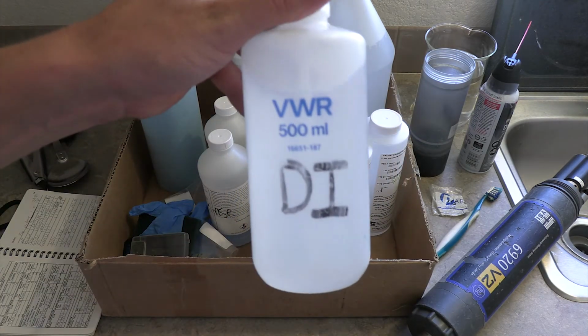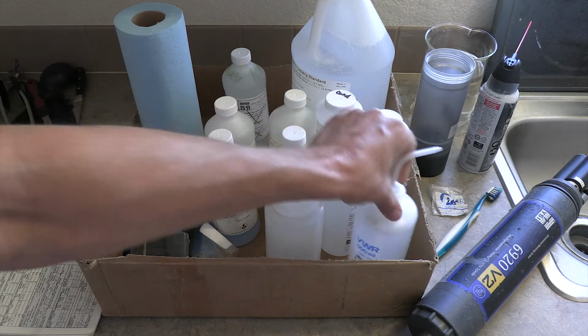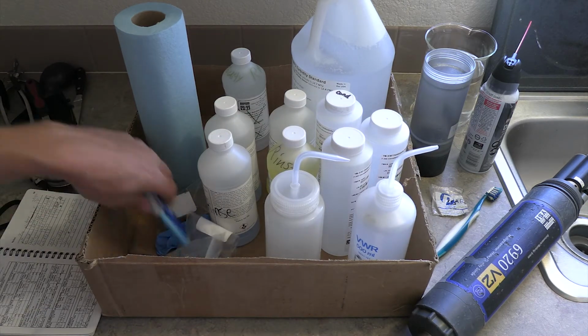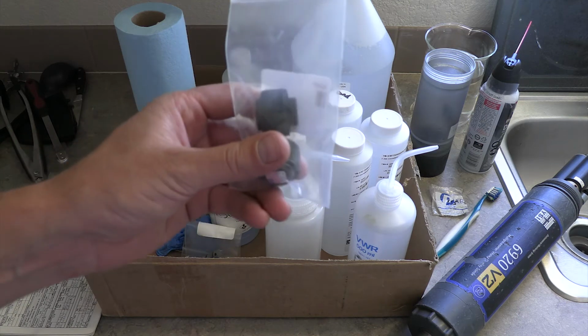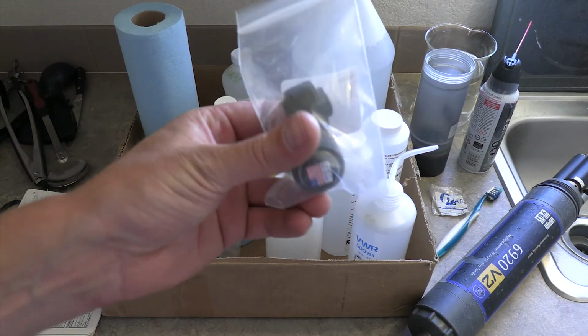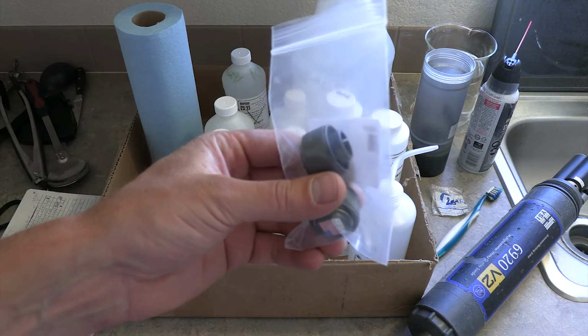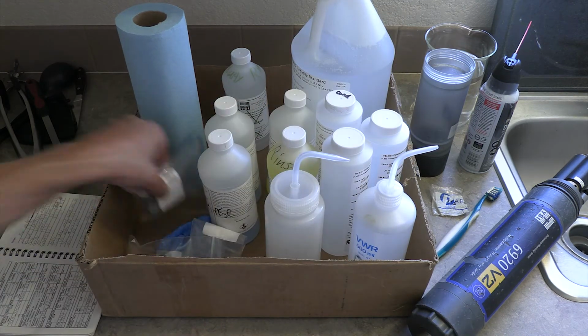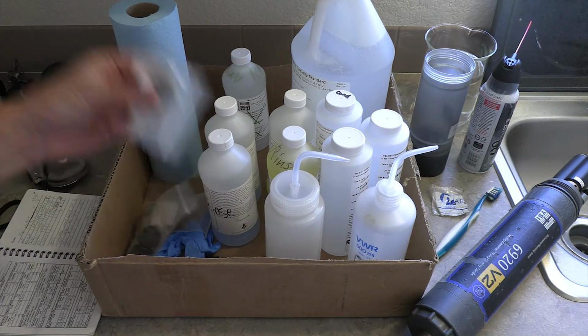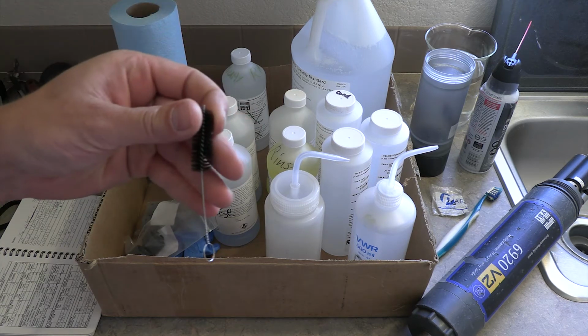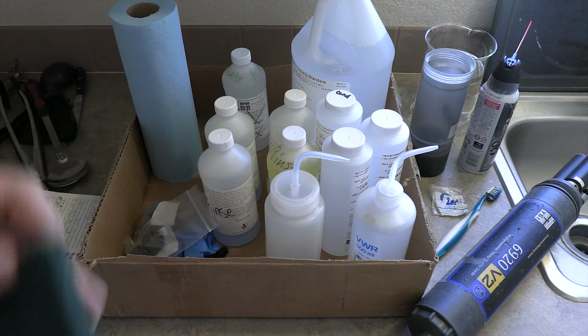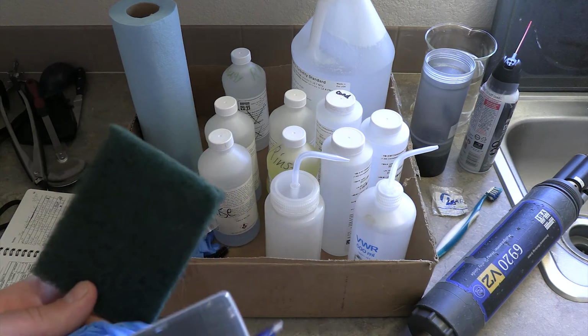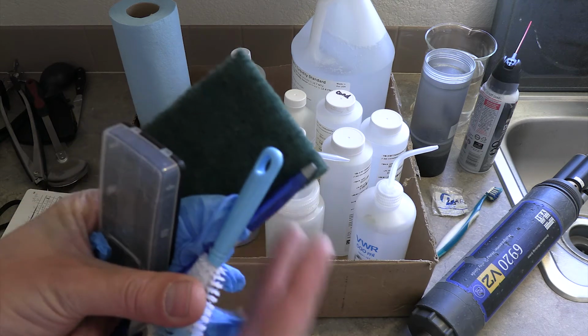And then also DI water, just for cleaning the joints as well. But to look at it really quick, we do have some other pieces in here: an extra pen, and plugs if we want to clean the sensors. We can remove the sensors and cover the sensor port with a probe cover. Same thing for a different size. We've got gloves, industrial paper towels for cleaning, and other brushes, there are more brushes to clean if you need it, and a scrubby pad to clean in between the ports, and a few extra port pieces. So yeah, that should do it. On to the next piece.